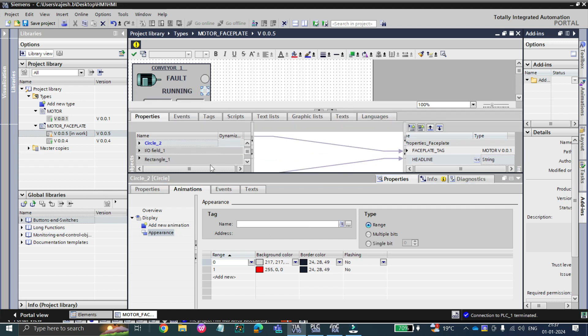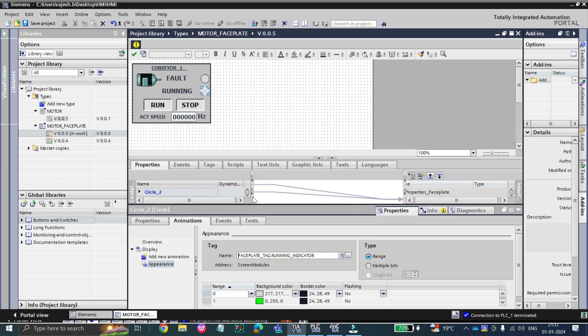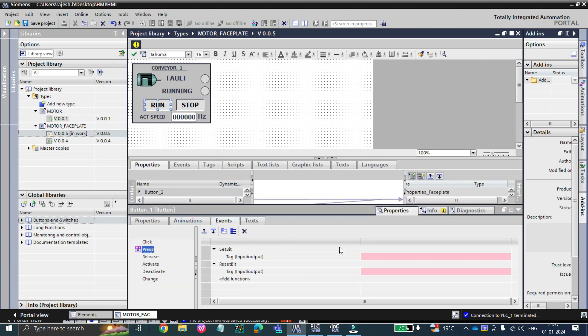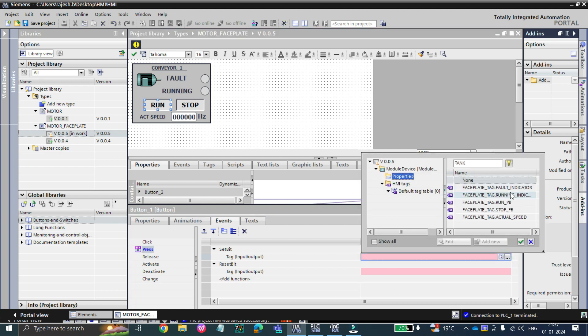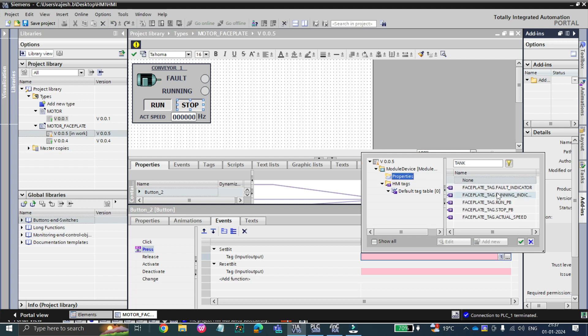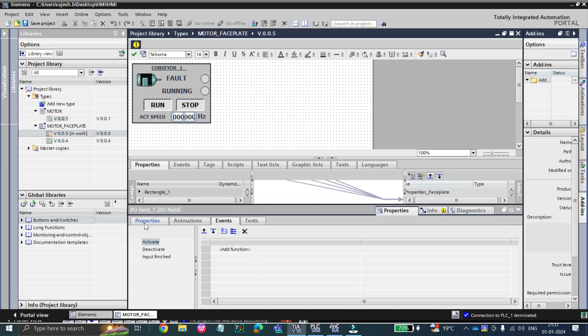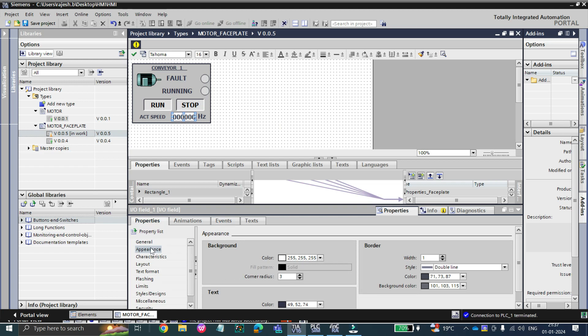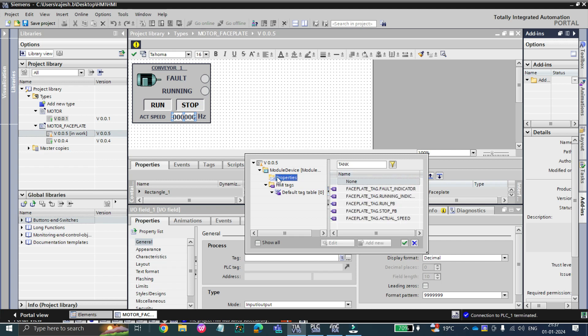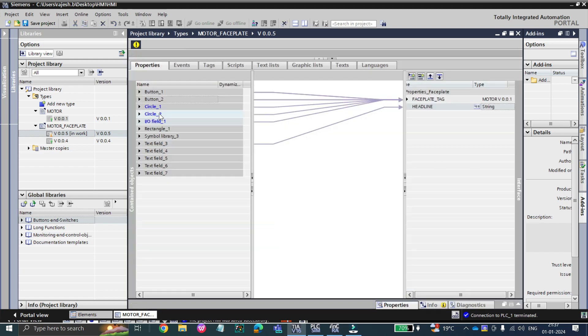Similarly, let's give the animation for the running indicator. For the run events, go to the event for the run push button and set the property tag to 'run push button', and reset the stop push button. Similarly for stop, set the stop push button tag and reset the run push button. At actual speed as well, go to properties, general, and under tag choose 'actual speed'. Now you can see all the tags are connected to only a single tag, and inside it they are distributed automatically.